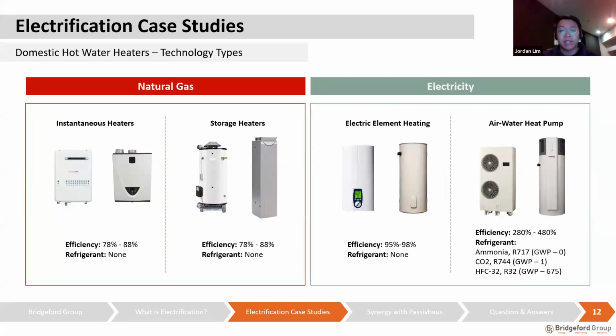Now, for domestic hot water assets, on the left of the screen here, I've provided some gas-fired domestic hot water technology that are quite conventionally applied. You can see that on average, the efficiency is only about 78% to 88%. And the electric alternatives would be either to use electric element heating technology or to use heat pumps. And you can see here, there's actually not much difference in efficiency gain for electric element heating compared to conventional gas technology. But with heat pump, depending on the refrigerant that is being used, the average efficiency, or what we call COP, coefficient of performance, can range from 280% all the way up to 480%.